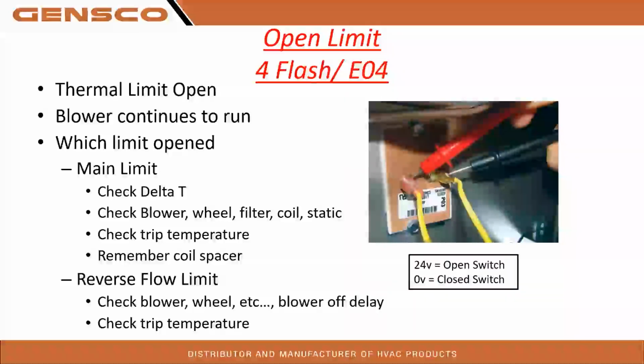Coil spacer, it says remember coil spacer, that would be on the 17.5 wide furnaces and the downflow application. So they wanted a 3-inch spacer between them. So reverse flow limit. So we're going to check blower wheel, blower off delay. Maybe we're keeping the off delay not on long enough. Of course, we're going to check the trip temperature.